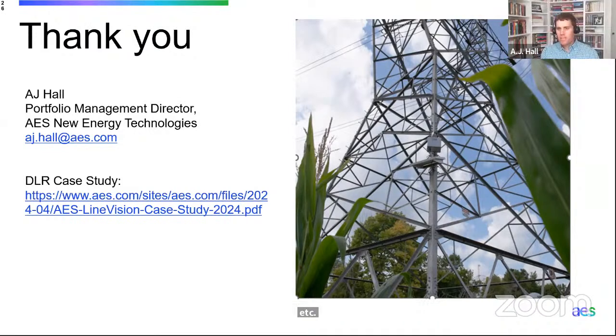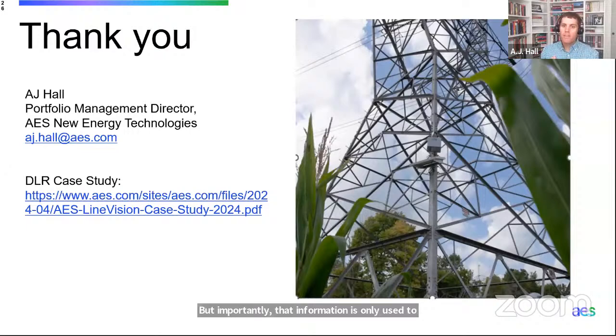So the sensor you can see on the screen here, in that silver box in the middle, relies on cellular communications. That's beaming back the real-time sag and line blowout information from the field. But importantly, that information is only used to train the ratings algorithm. If there was a loss of a sensor in the field, say a farmer came in and took out a sensor, it's not going to affect the delivery of the dynamic line rating because the algorithm has already been trained on the information from the field.